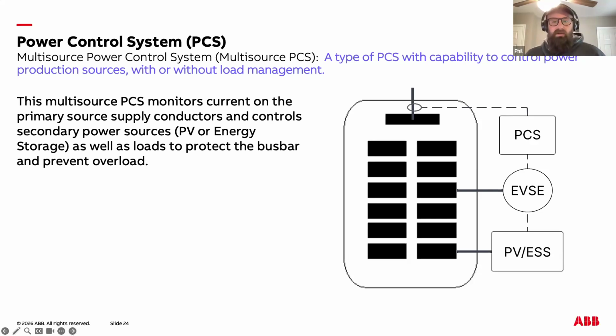Just like our last example, the PCS continuously monitors the current flowing through the primary service or feeder conductors, watching for any condition that could push the bus bar beyond its rated capacity. When the combined demand of the utility supply, PV ESS output, and EV charging begins to approach that limit, the PCS can automatically intervene. Depending on real-time conditions, it may curtail PV production, reduce or pause EV charging, or do both simultaneously.